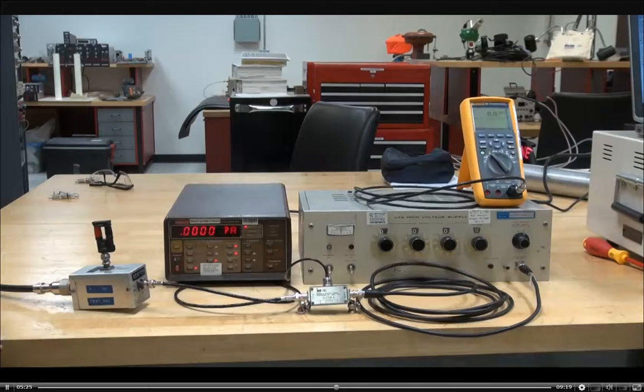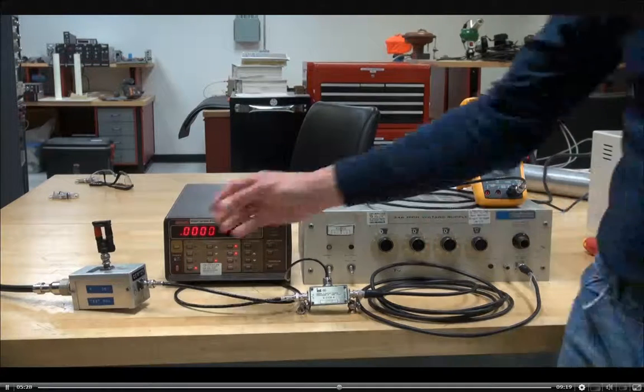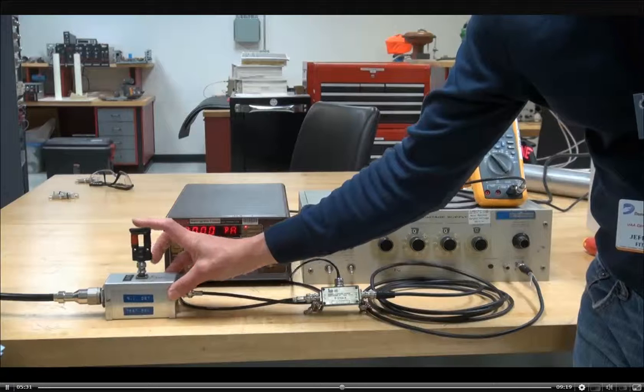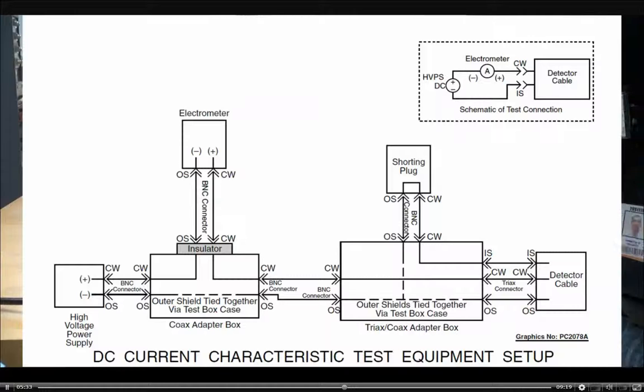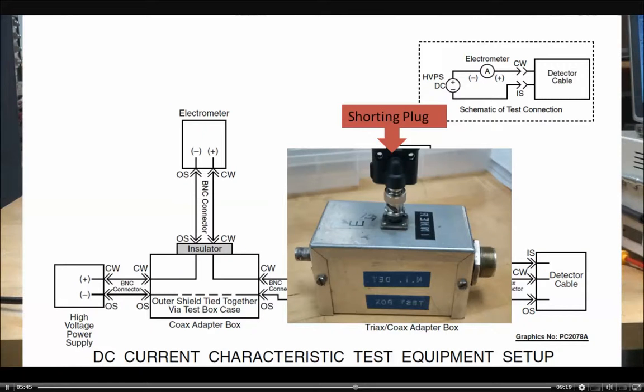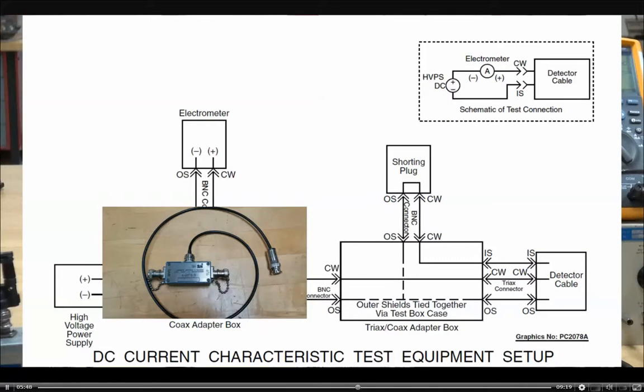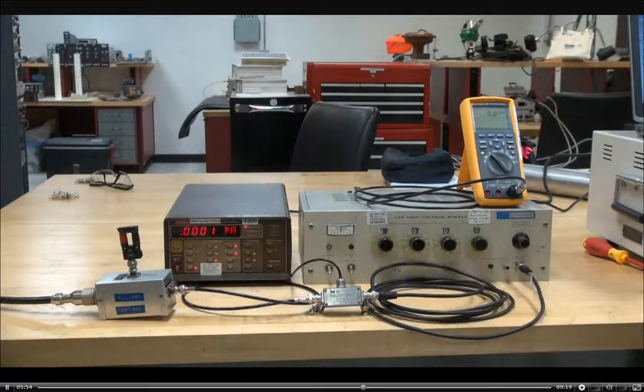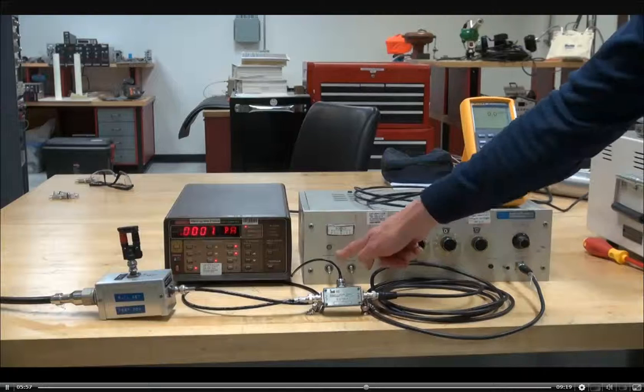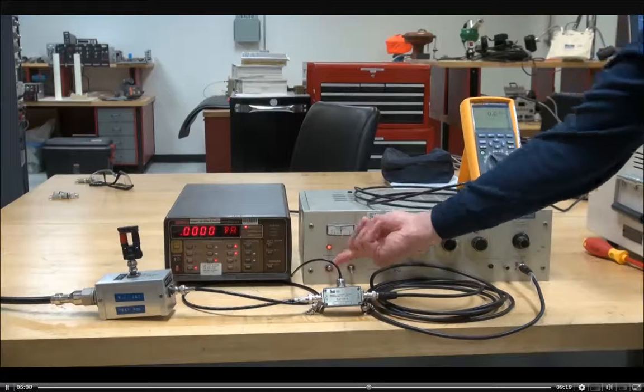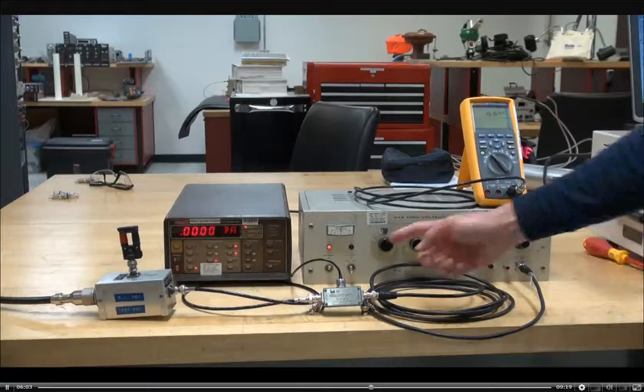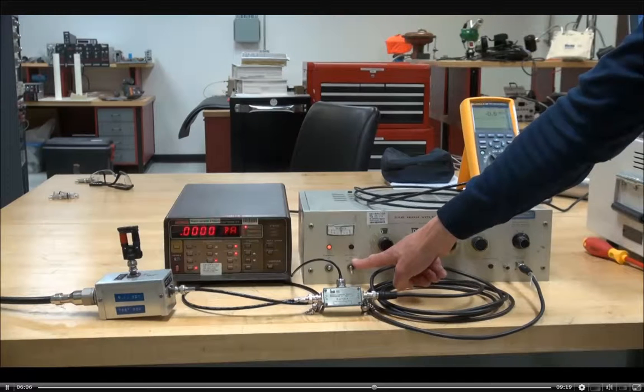Okay, and then connect shorting plug on position echo of triax to coax adapter box. So here is our shorting adapter connected. So now we have a continuous path that goes through the high volts power supply, through the electrometer, through the detector, its gas space, and then returns back. We have a completed loop. Turn on output of variable high voltage power supply. Alright, so the high voltage power supply, I'm going to turn it on. And the procedure tells me to turn the output on.